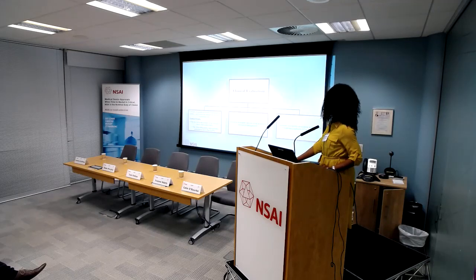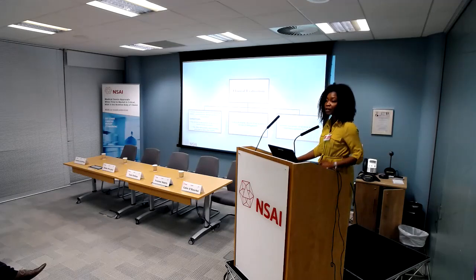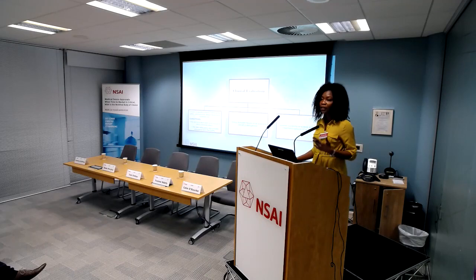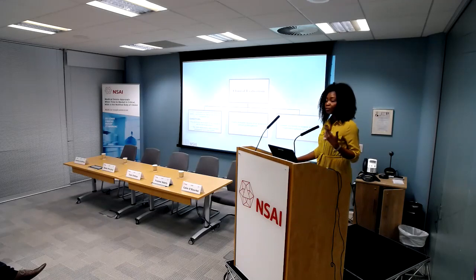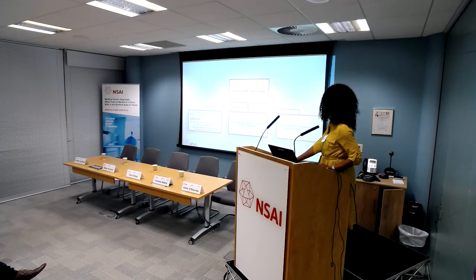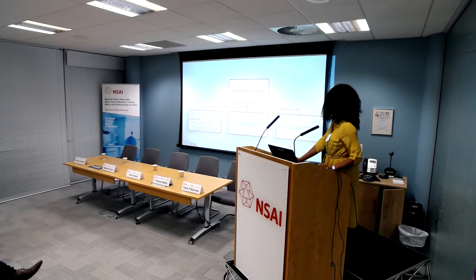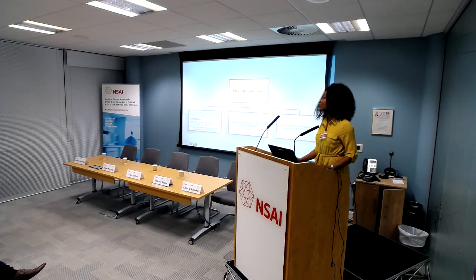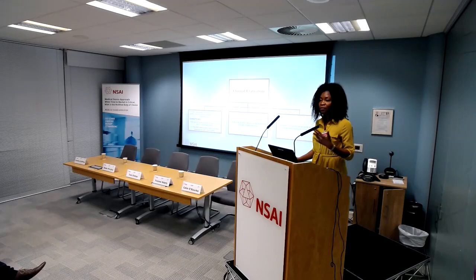Also, you can base your clinical evaluation on clinical investigation. That's you going out to perform a clinical trial regarding your device, in order to prove to us the safety and performance of your device, that you have data related to its safety and performance, and that it performs as intended under normal conditions of use. And you can also search for other alternative treatments that would be similar to your device, if they are available. Obviously, if it's a novel device, there are no alternatives. Then there's no device like yours.